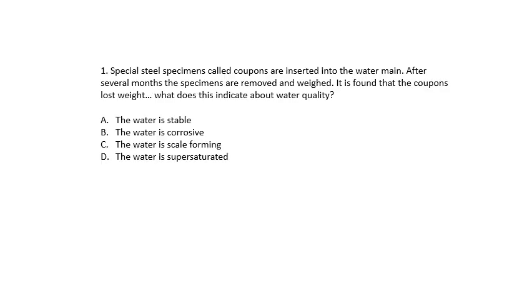Question number 1. Special steel specimens, called coupons, are inserted into the water main. After several months the specimens are removed and weighed. It is found that the coupons lost weight. What does this indicate about water quality? That the water is stable, corrosive, scale forming, or super saturated. The answer is the water is corrosive. The coupon lost weight means it got corroded. If it's stable, the weight does not change, and if it's scale forming, it will gain weight.